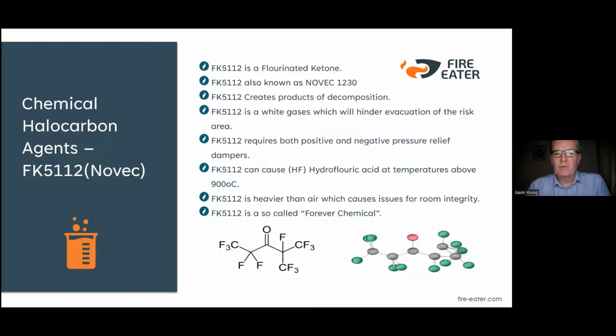Novec, or FK-5-1-12, is a fluorinated ketone. It creates products of decomposition just like FM200. It's also a white gas. What you need to consider when you're looking at FM200 and Novec is if you've got a very large space like a data center, when the gas discharges, you won't see your hand in front of your face because it fogs up the entire space, so it would hinder escape.